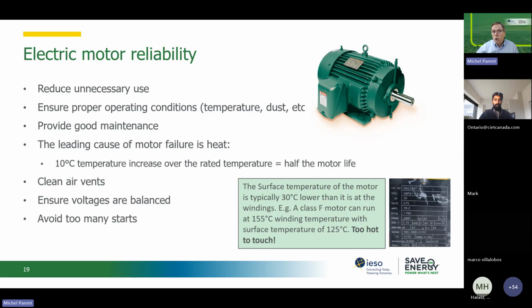There's other reasons why it could be running that hot. If it's a three-phase motor, it could be a voltage imbalance in the three-phase that could lead to this kind of hot operation of the motor. But that's one item that's often overlooked. And if you do have that little infrared camera, the diagnostic can be done once a year very quickly on all your motors. Just provide the right tool to your operating team.